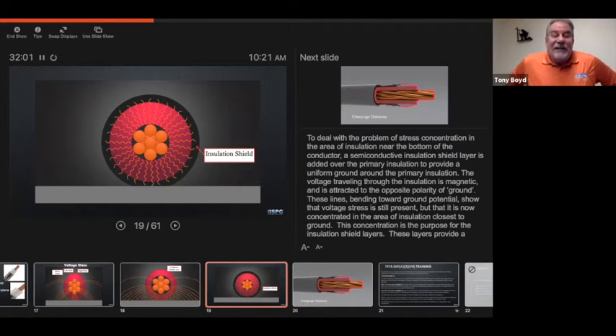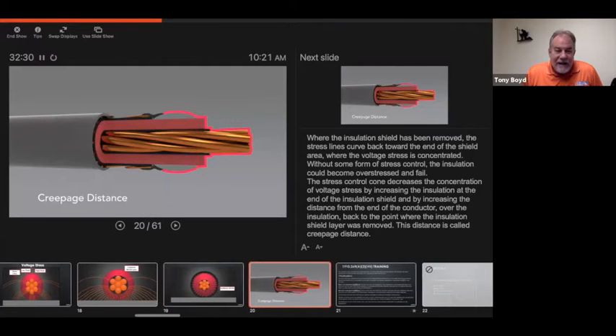All right, so the insulation shield actually makes the stress lines go out evenly. So, to deal with the problem of stress concentration in the area of insulation near the bottom of the conductor, the semiconductor insulation shield layer is added over the primary insulation to provide a uniform ground around the primary insulation. So that is why it is so important not to nick this insulation shield when you're skinning back the cables. And I'll talk a little bit more about that in a minute.